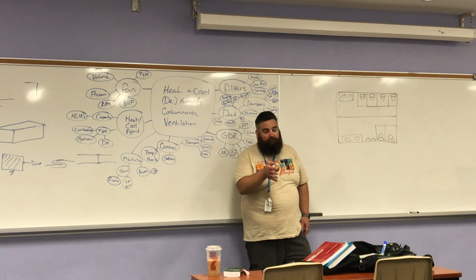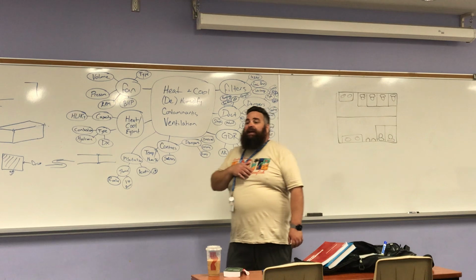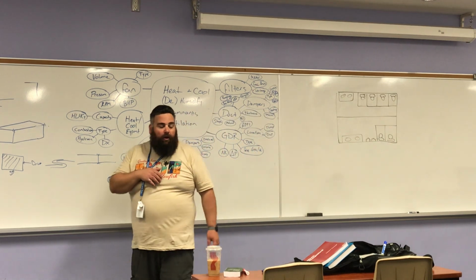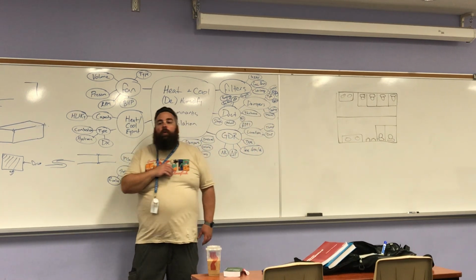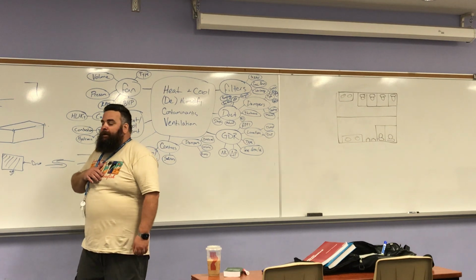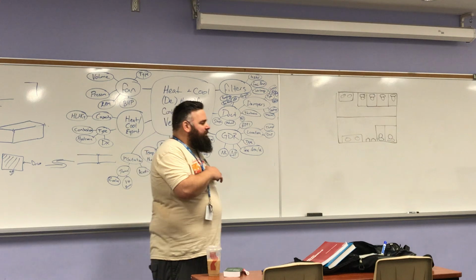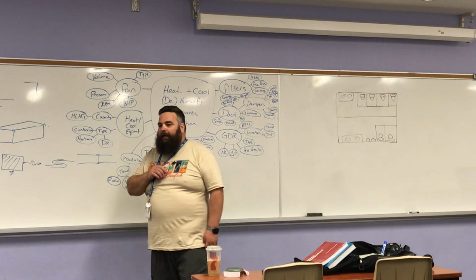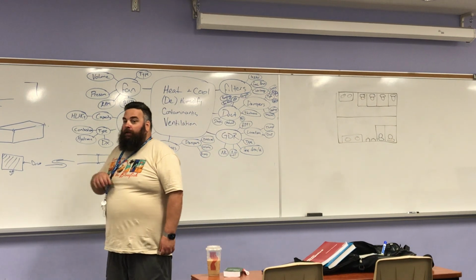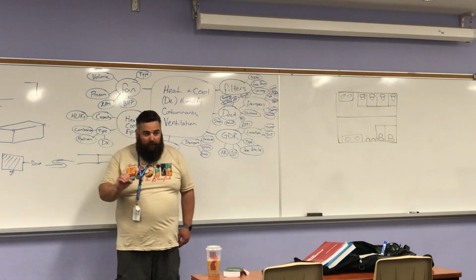You're right. We are going to look at a standard, and this is something you'll want to write down, called ASHRAE 62.1. ASHRAE 62.1 is ventilation for acceptable indoor air quality. Keyword: acceptable.